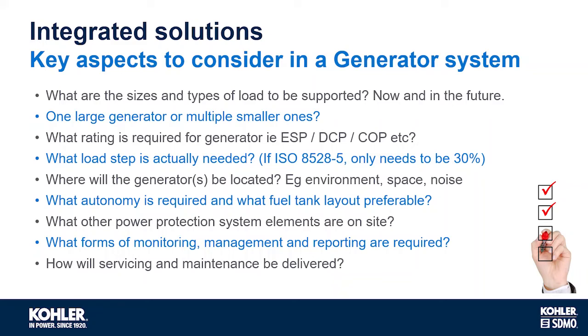Thanks for that. So some key aspects to consider on the generator system. What are the sizes and types of loads to be supported now and in the future? Should it be one large generator or multiple smaller ones? What rating is required? ESP, data center continuous or continuous operating power. What load step is actually needed if ISO 8528 only needs to be 30% to comply? Where will the generators be located, e.g. the environment, the space and noise requirements? What autonomy is required? What fuel tank and fuel system layout is preferable?